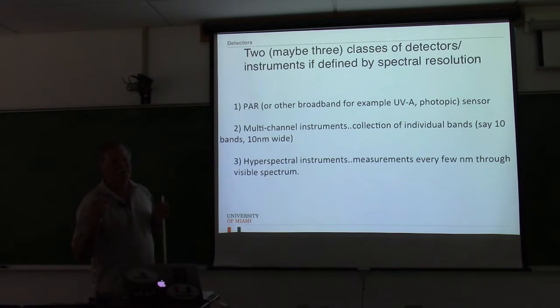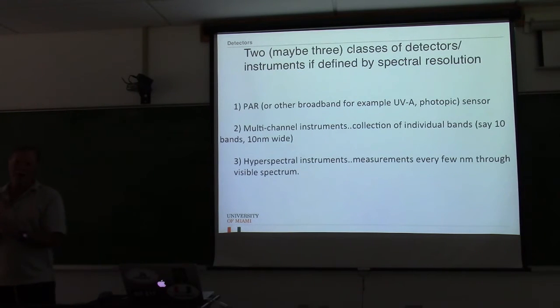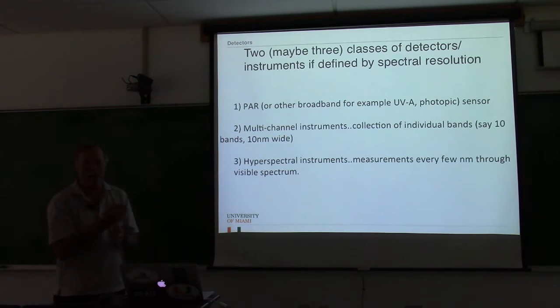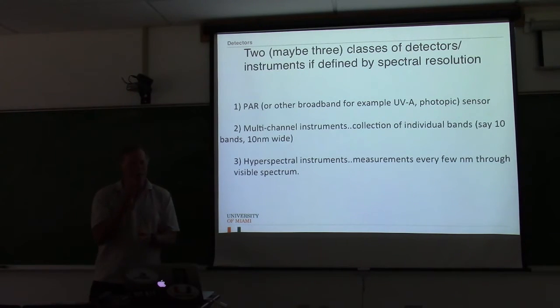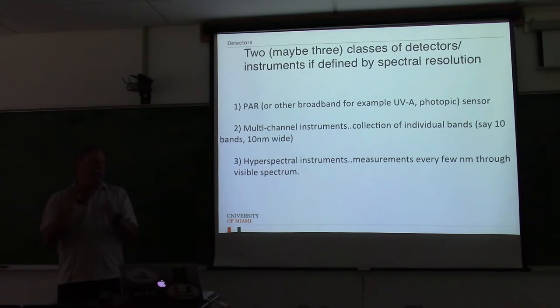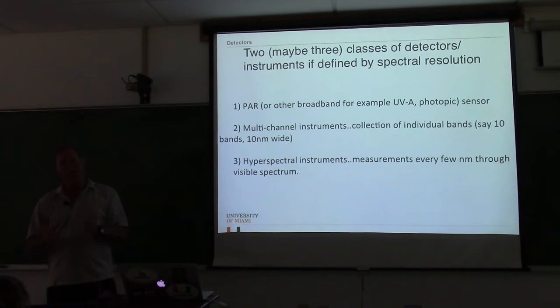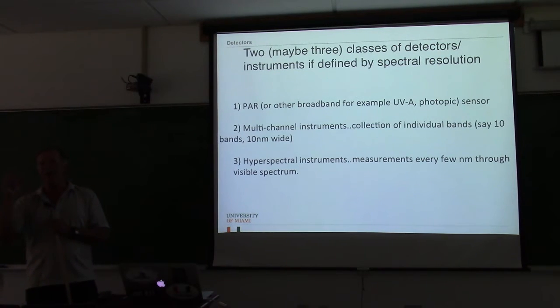But when you have a hyperspectral instrument, we'll use gratings or prisms or something to disperse the light. And then you have a whole bunch of detectors behind there. So eventually you have detectors spread through the wavelengths, and these detectors will have a spectral bandpass that they're detecting, that you should describe in terms of its full width at half maximum and such.